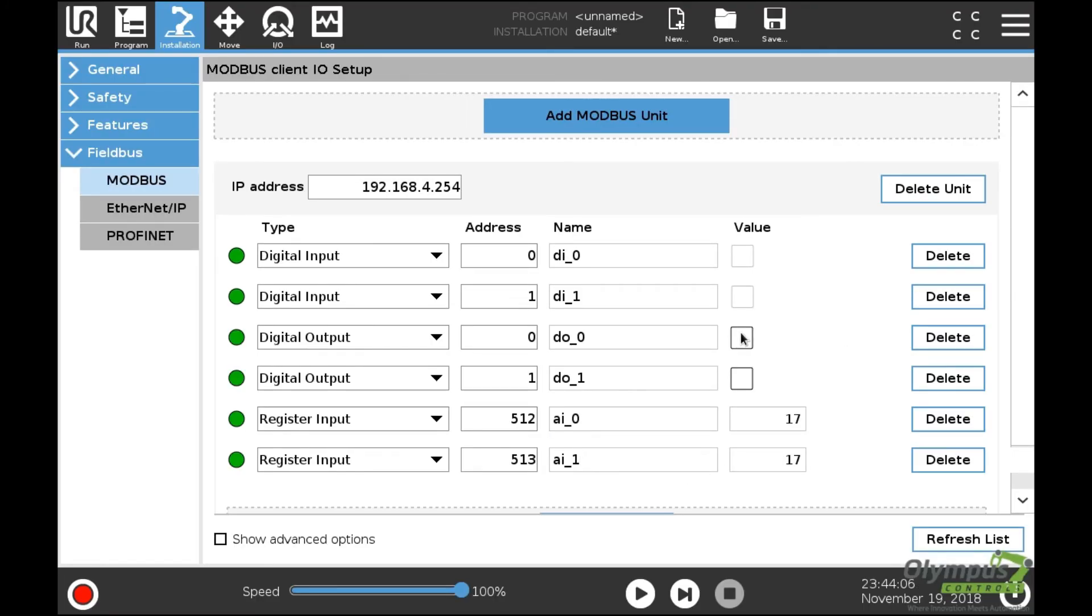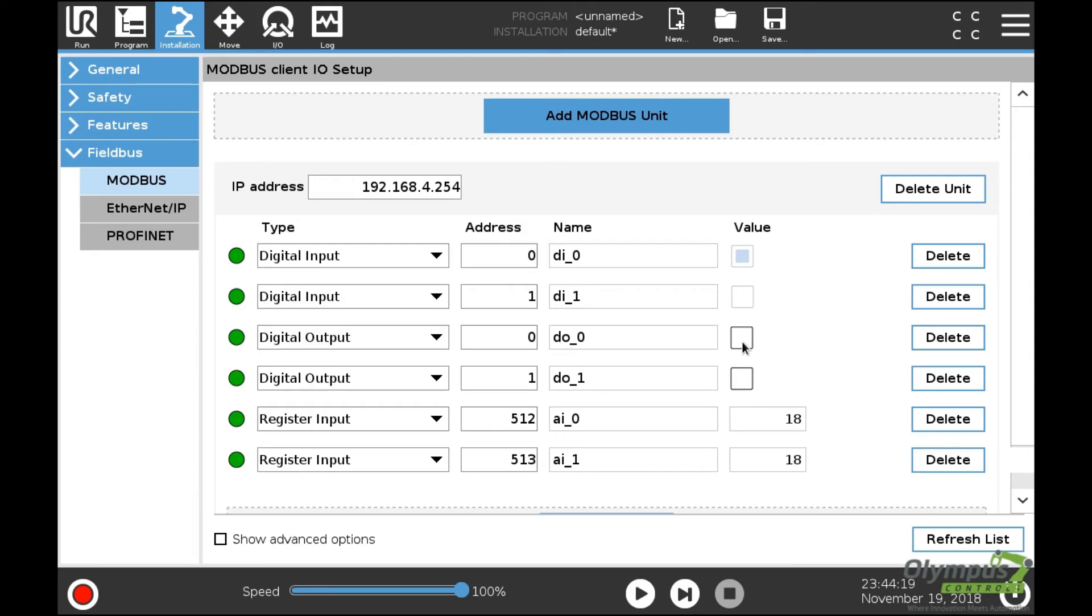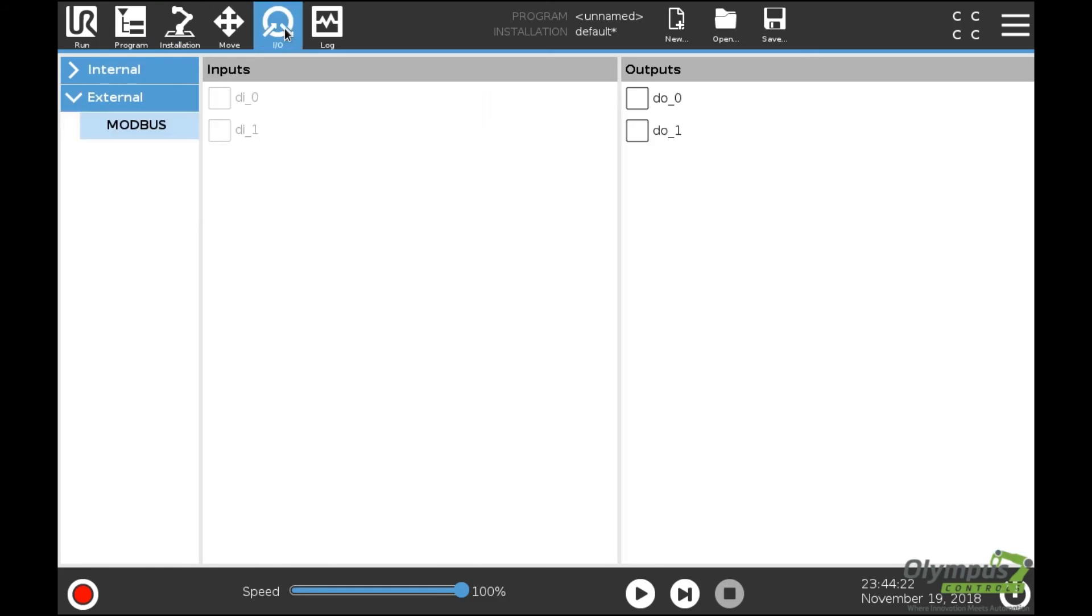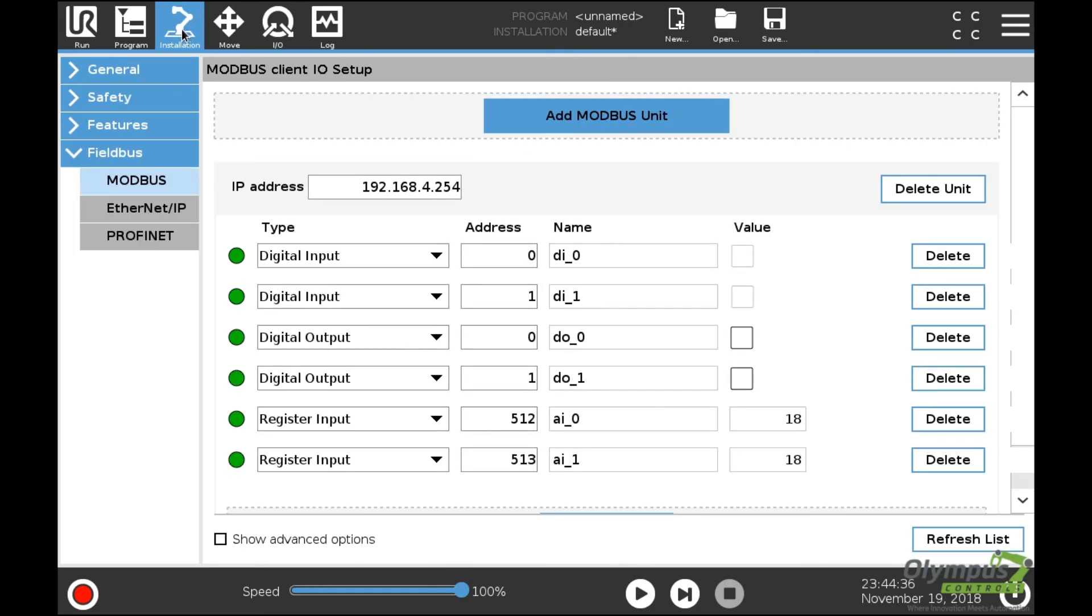If I click this, you'll notice the input will go high because I have them jumpered together. If I set the output on the first one, nothing happens besides setting that output high since it's not tied to anything. I can also view my Modbus signals in the I/O tab under External and Modbus. Setting digital output zero makes digital input zero go high.